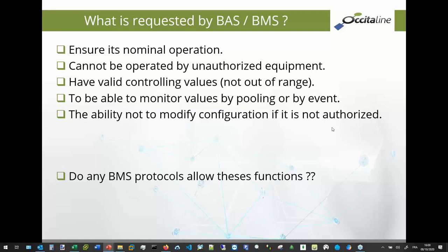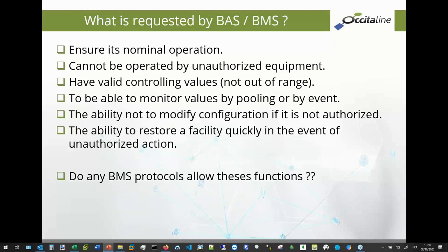Another thing is to be able to monitor values by polling or by event. I explained just before the two different visions of the SCADA or on field, for the vertical communication or horizontal communication or interoperability. Some protocols do not have polling and do not have binding. It's critical in some usages.